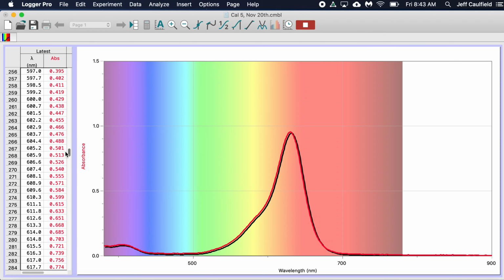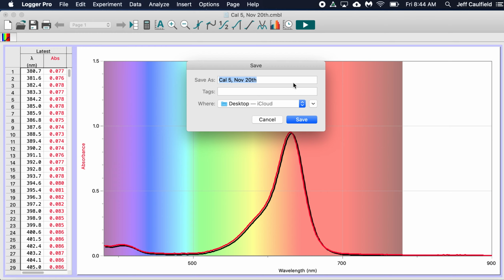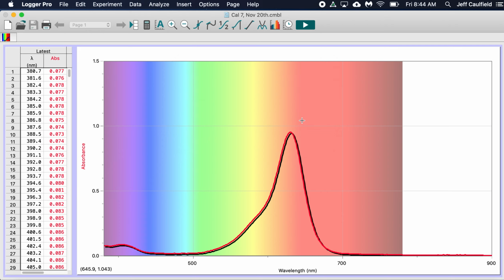What I would do is graph up my calibration curve and see if I had any reason to believe that it was falling off of linearity. But this is 0.953. This was the 7 parts. Okay. All right, so this is how good my calibration curve is right now. It is good up until I get right around 1, because that was the highest one that I'm going to use here.